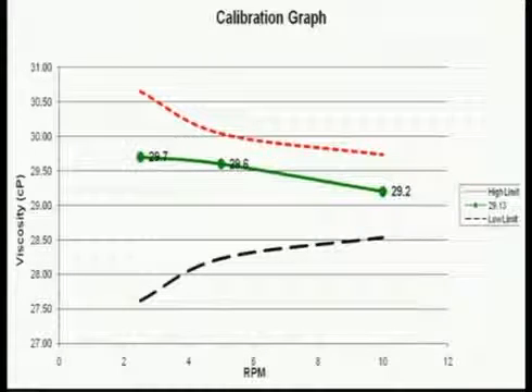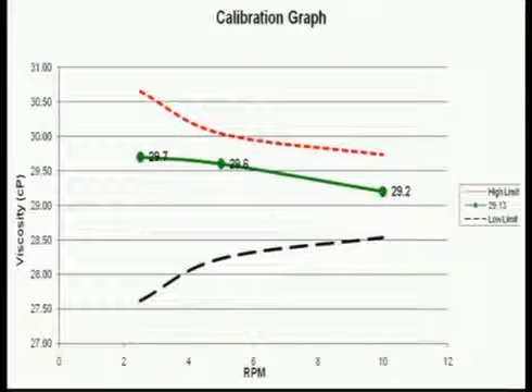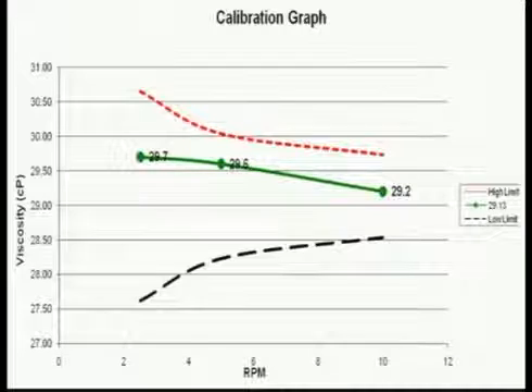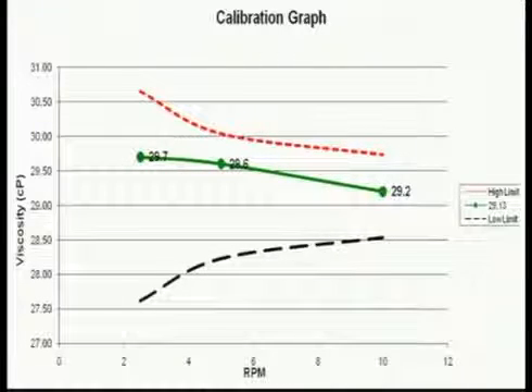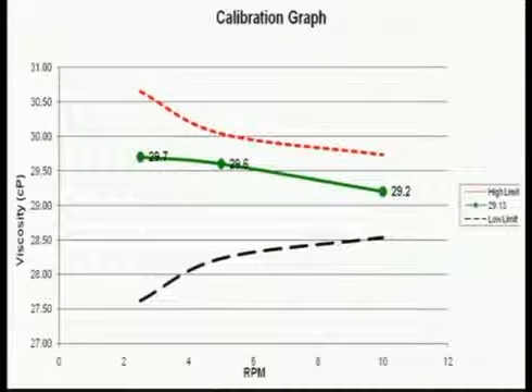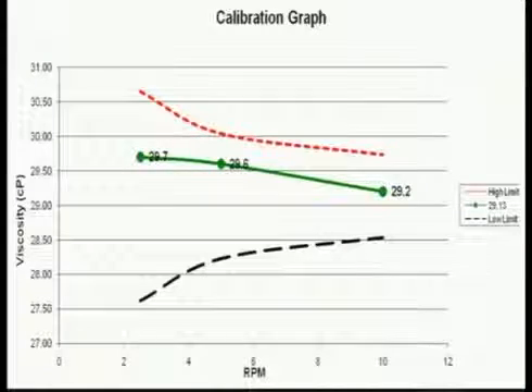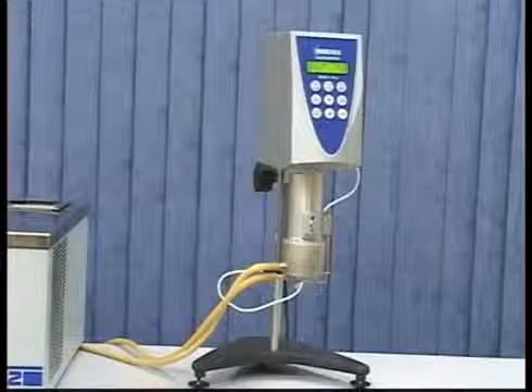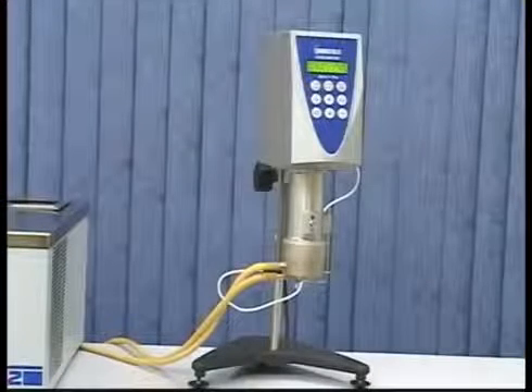You can see a graph of your results with this worksheet and the tolerances. Select the Calibration Graph tab to view the results. The data points are plotted and upper and lower tolerances are shown. In this example, you can see the data points came within tolerance. And that's it. You have performed a cone plate calibration check.